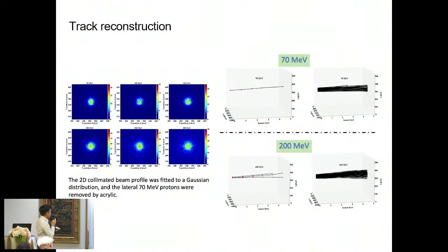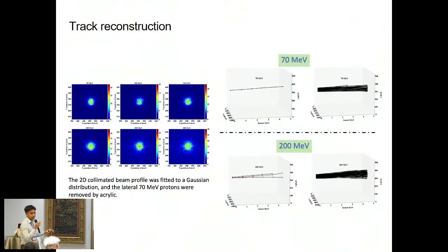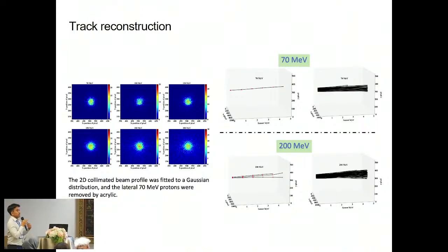And this is our result. Actually, this is a super preliminary result. We have the proton beam passing through the collimator, and we have 6 points here from the sensors that we have. He produced the algorithm to track the proton, and here is the proton that he can really track without any phantom, without any absorber. This project is still going on and not finished yet. I would say this is kind of the progress of this project.